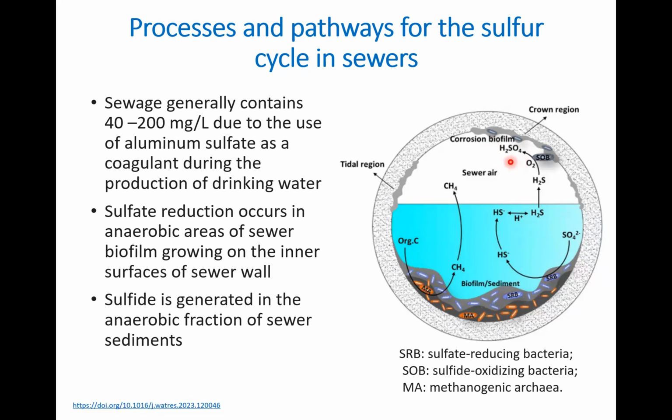And of course, this sulfuric acid can cause corrosion to the containers or the pipes or the tubes that have this wastewater flowing through them. Also, if you have organic matter, it can undergo methanogenesis and produce methane as well inside this kind of confinement.